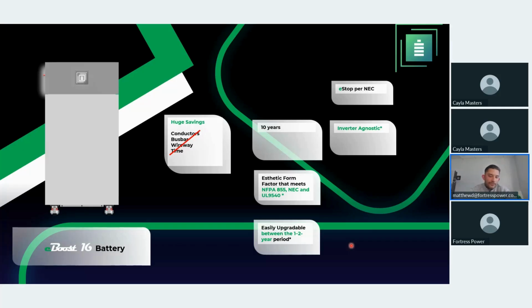As you can see, the battery solves a lot of the aesthetic form factor concerns, and is a perfect aesthetic form factor for many of the jurisdictions and new regulations that are coming up, right? You have NEC code, or applications where batteries have to be installed 3 feet above the ground. This would certainly meet that, where the disconnect is not higher than 6.7 feet, and it would save the installer from having to install bollards when installed inside a garage, right? And it will meet UL 9540 DC ESS, okay?